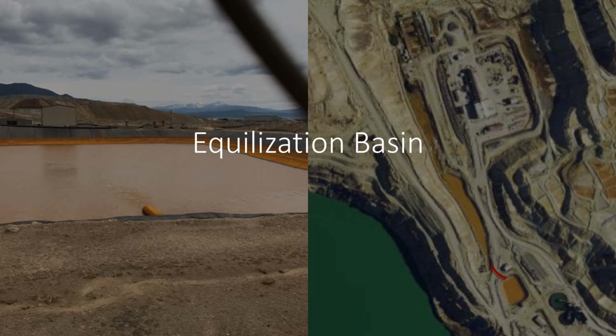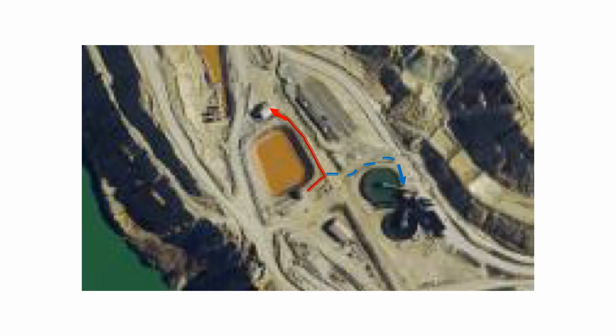ponds. From the bottom of that red line on the last slide, the Horseshoe Bend area water makes a jump into the equalization basin, which you can see pictured on the left. From the equalization basin, the mine does have the ability to run that water separately through the Horseshoe Bend water treatment plant, or it can be blended with Berkeley water, just depending on the water needs of the site. But typically that water is pumped from the equalization basin to TK1, which is that little building north.